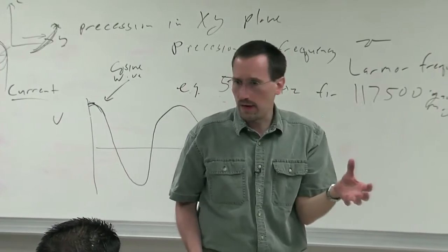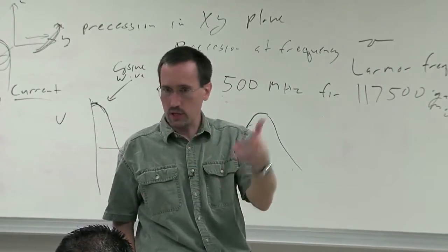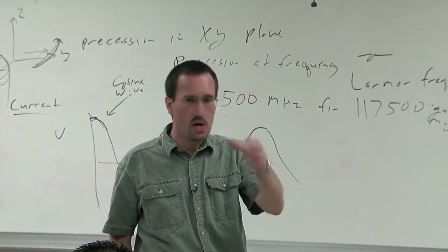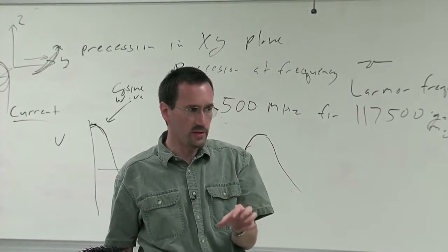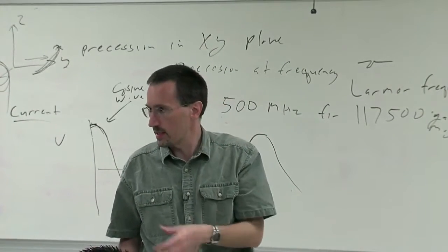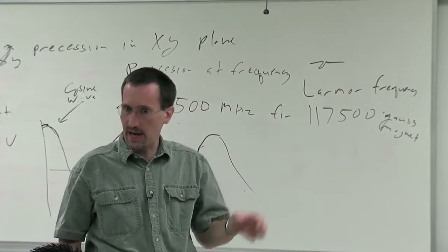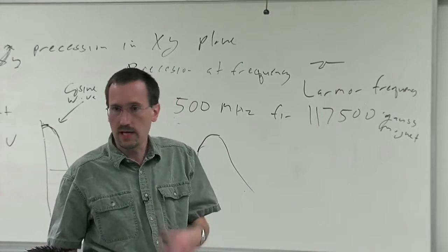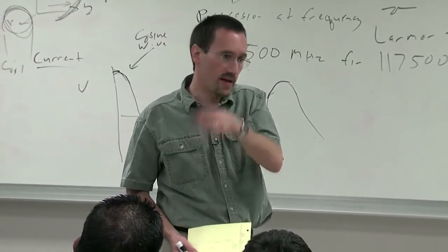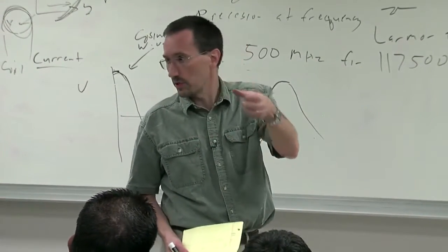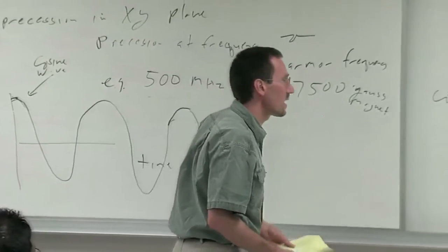That comes back to what I was saying before about, remember I mentioned broadband detection and the proton coil? So in general, different coil shapes work well for different frequencies. And so one coil's on the inside. And so if we are doing proton NMR, it's best to have your proton coil on the inside. If you're trying to get the best carbon NMR, in general, it's best to have a coil tuned to carbon's frequency on the inside. Remember, they differ by a factor of 4.